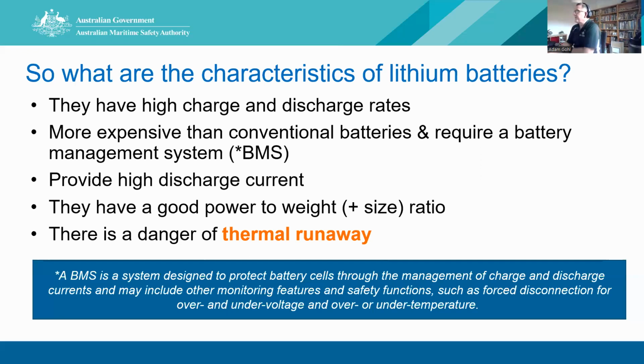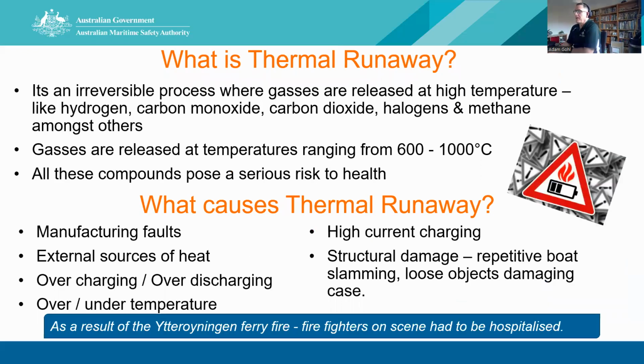Thermal runaway - that picture on the first screen was of a battery in thermal runaway. It's an irreversible process where gases are released at high temperature, like hydrogen, carbon monoxide, carbon dioxide, halogens, methane, amongst others. They are released at temperatures ranging from 600 to 1,000 degrees centigrade.